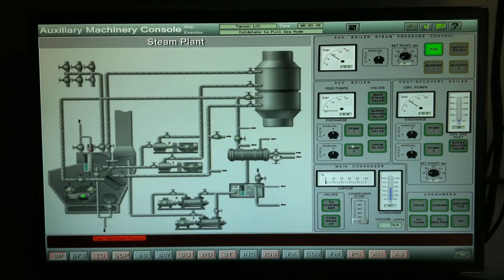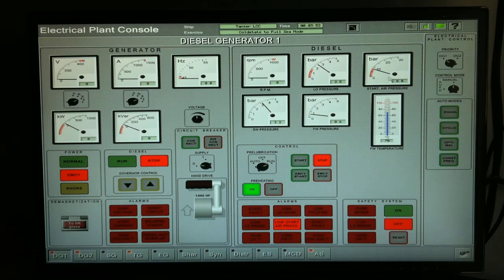Okay, we check back, go back to our generator. Okay, so 8.0, 8.1 bars, that's enough for starting. All we need to do is wait for the pressure to raise to around 8.5 bars. Once we have 8.5 starting air pressure, the alarm will be cancelled out and you could already start your generator. Just press start.